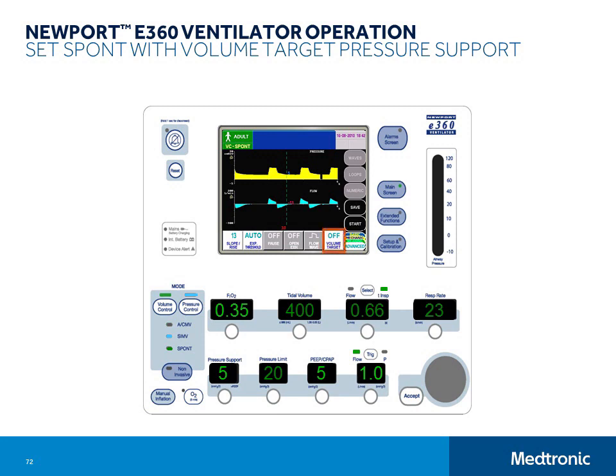On the other hand, if you want to use volume target pressure support rather than standard pressure support, choose either the volume control or pressure control SPONT mode and make sure that volume target is turned on in the advanced data set. In this case, the pressure support control will not be active, and you will set the pressure limit as the maximum pressure level that the ventilator will target for each pressure support breath. Remember that in this breath type, the ventilator will choose the lowest pressure support level that will achieve the tidal volume you set.